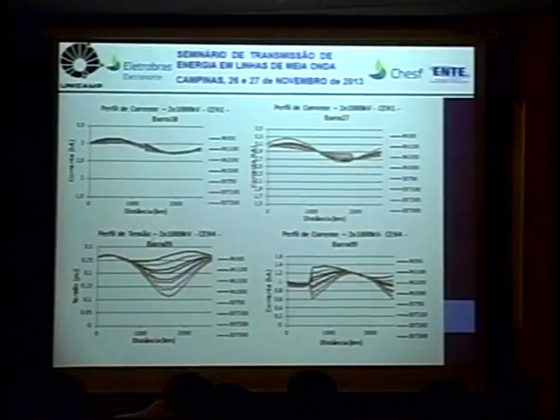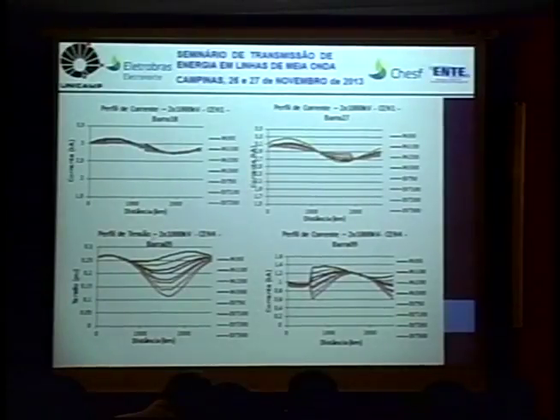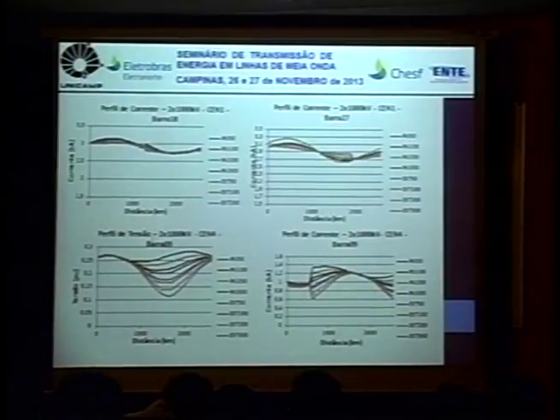Here, in a scenario with a low amount of load in the line, around 800 megawatts, when I extract, varying from 50 to 300 at 1/4 of the line, I can see that the voltage profile is going to be very different from when the profile was adjusted and optimized. The same thing for the current profile. I can see that I have a more significant impact on the current profile, because here the line has a low amount of load. So if I extract 300 megawatts, I'm going to have a higher impact.